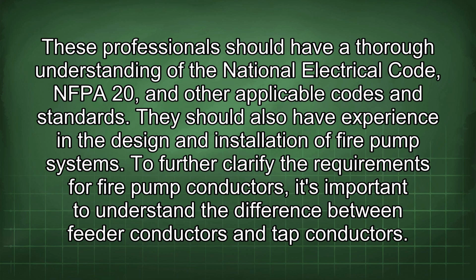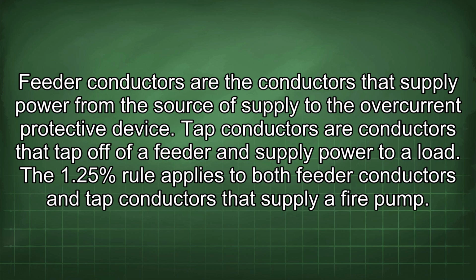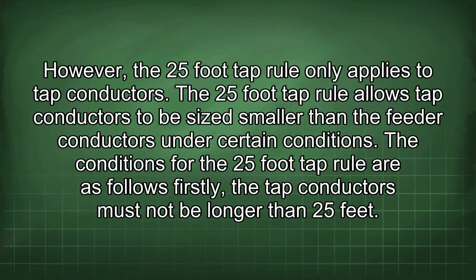To further clarify the requirements for fire pump conductors, it's important to understand the difference between feeder conductors and tap conductors. Feeder conductors are the conductors that supply power from the source of supply to the overcurrent protective device. Tap conductors are conductors that tap off of a feeder and supply power to a load. The 1.25% rule applies to both feeder conductors and tap conductors that supply a fire pump. However, the 25-foot tap rule only applies to tap conductors. The 25-foot tap rule allows tap conductors to be sized smaller than the feeder conductors under certain conditions.